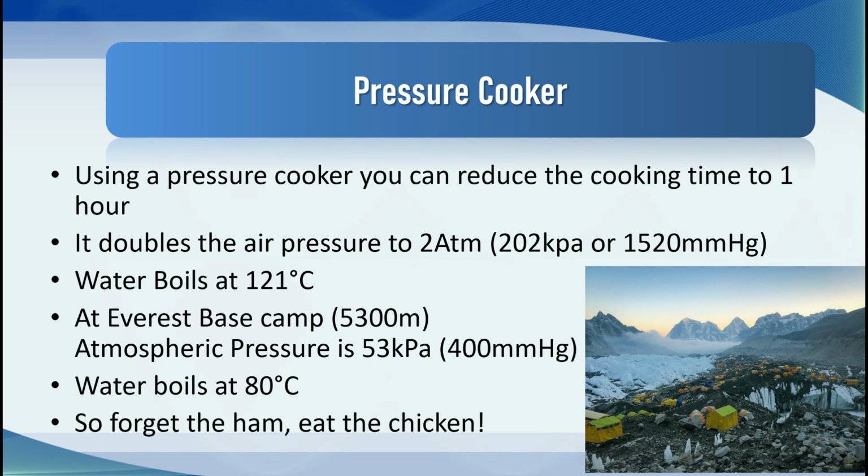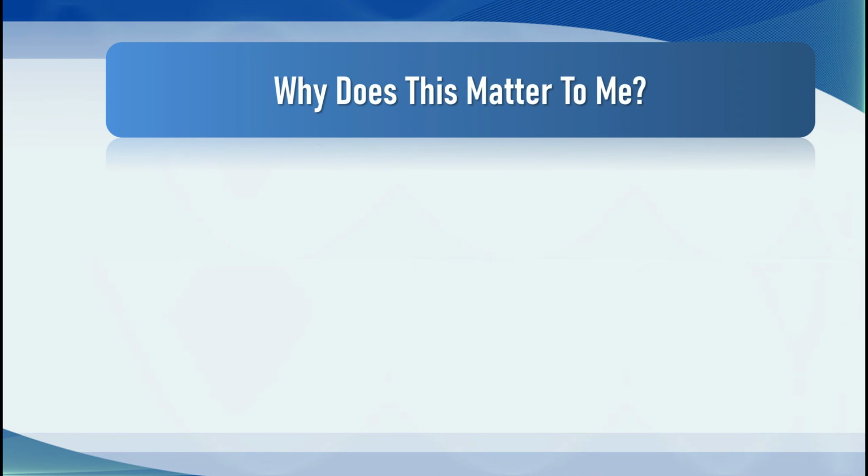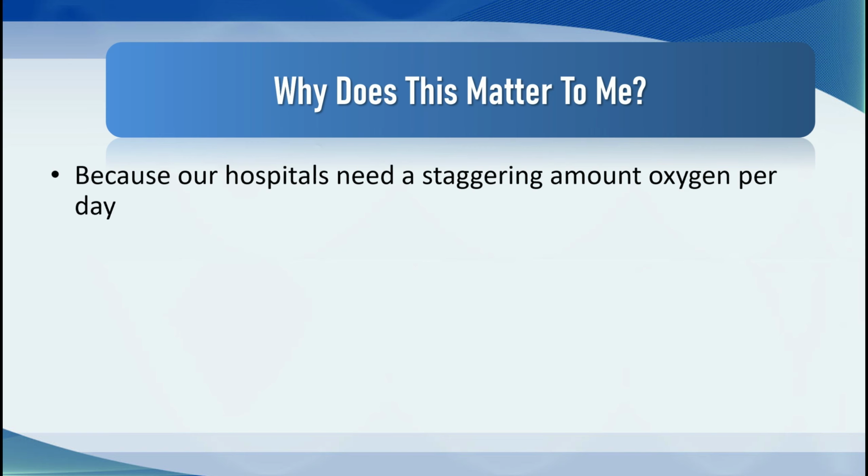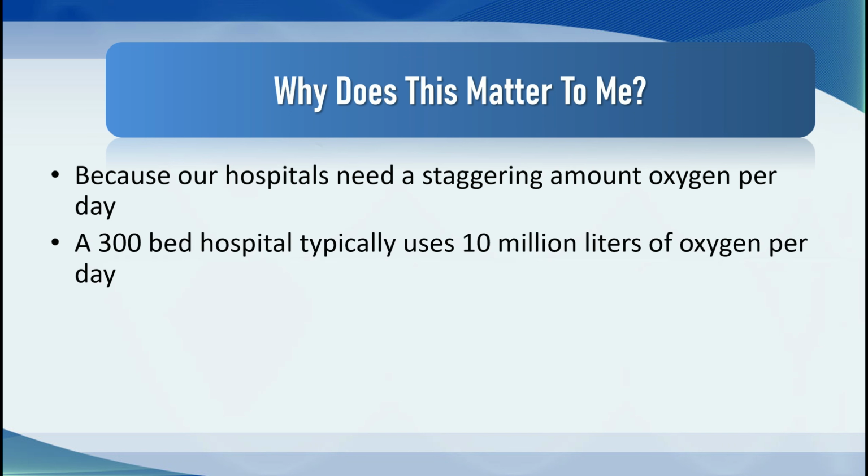But you're saying to yourself, this is not a home economics lesson. I'm an anesthesiologist. Why does this matter to me? And the reason why this matters is because our hospitals need a staggering amount of oxygen per day. A 300-bed hospital typically uses 10 million litres of oxygen per day.